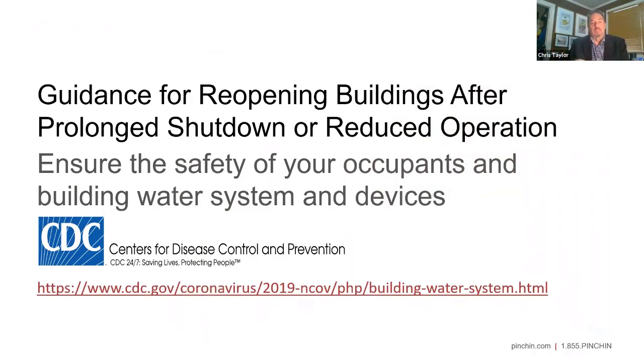So as Steve mentioned, there is some guidance. The CDC guidance is pretty good. When it comes to water systems, I see a note: chlorine absolutely has corrosion issues, depending on your factor. And there's safety aspects of using chlorine that I also get a little concerned about as a safety person, so I'm not necessarily keen on that shock chlorination approach. It's more about trying to get that efficacy aspect. But yeah, absolutely, chlorine is another compound that can cause corrosion, particularly on copper-based piping systems. So I recommend, the nice thing about this one is it's a free document that you can access that provides you some additional guidance.